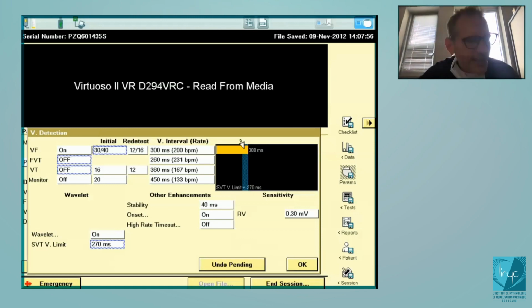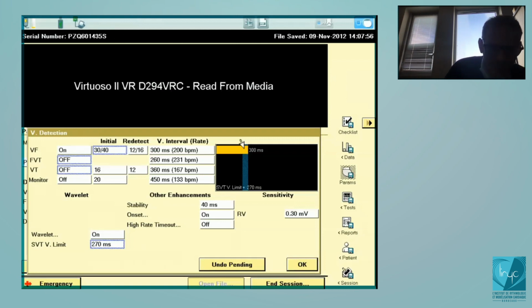So if you program it like this, you will systematically use the probabilistic counter. The probabilistic counter will work for very fast arrhythmia, but also for slower arrhythmia. If you program 188 beats per minute, the probabilistic counter will work perfectly. You will have the possibility, if you program before charging, to deliver two bursts, one before charging and then one during charging if the first one is inefficient. And you will also have the possibility to discriminate inside the VF zone.